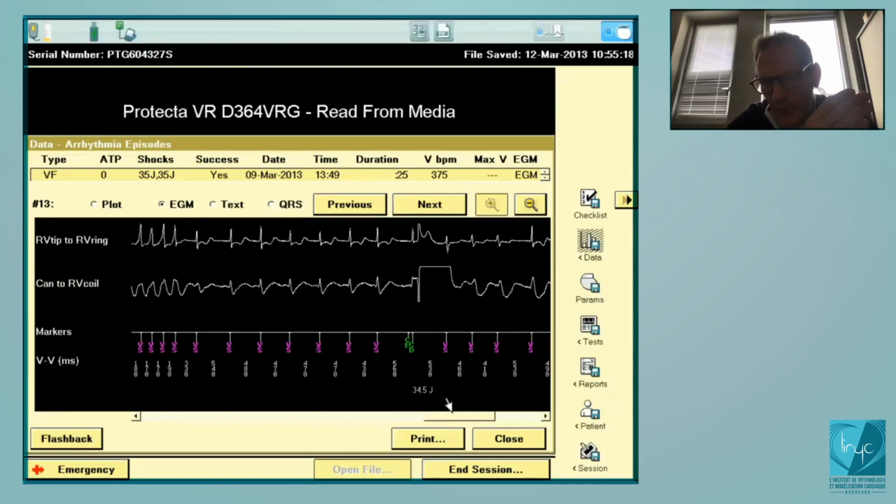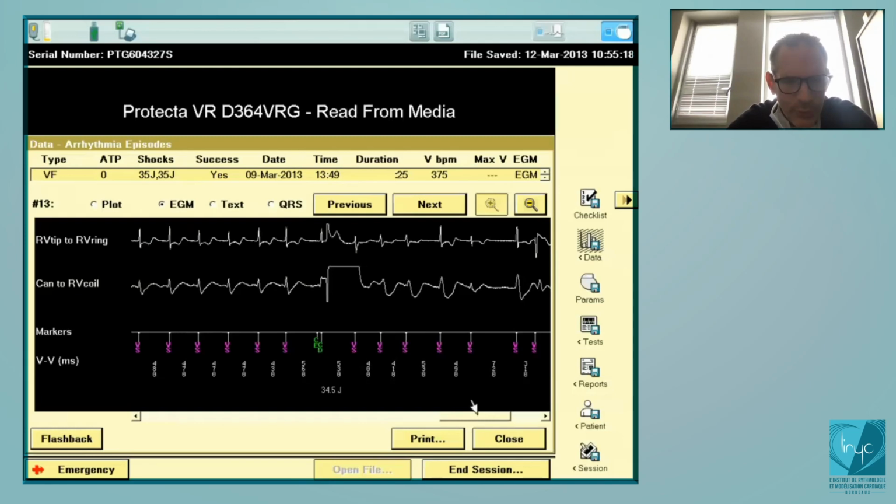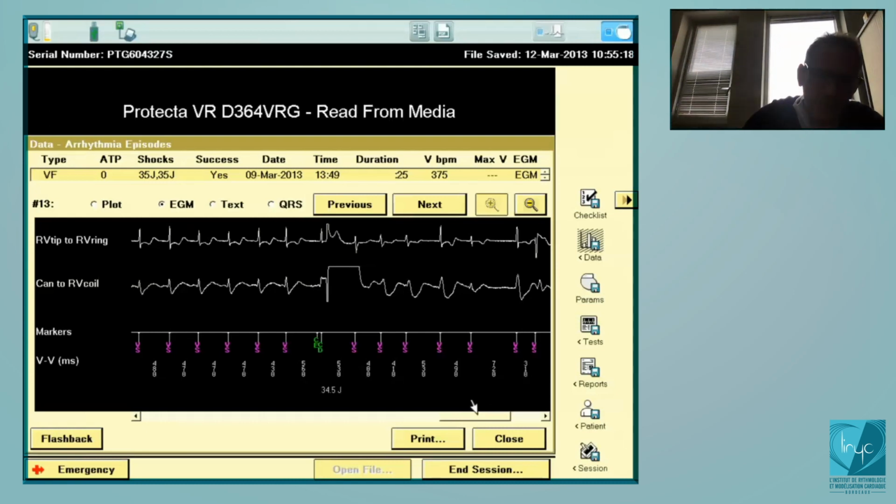And that's the same for number 2, number 3, number 4, number 5, and number 6. In Medtronic, you can only deliver 6 maximal shocks, but at the end of the charge, it will open a window of 900 milliseconds, and it will wait for spontaneous cycles in this window.